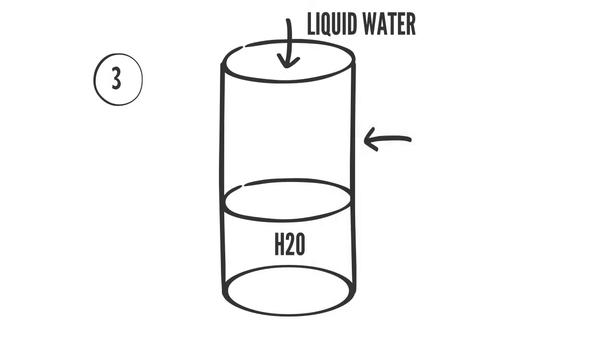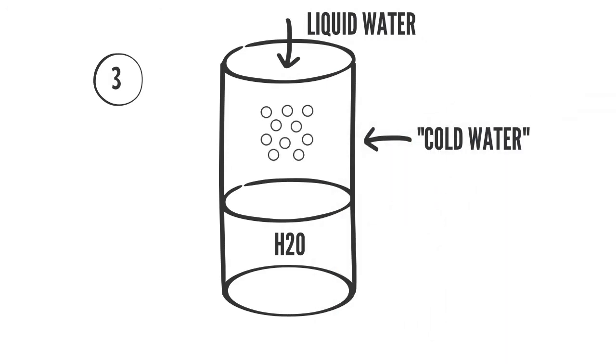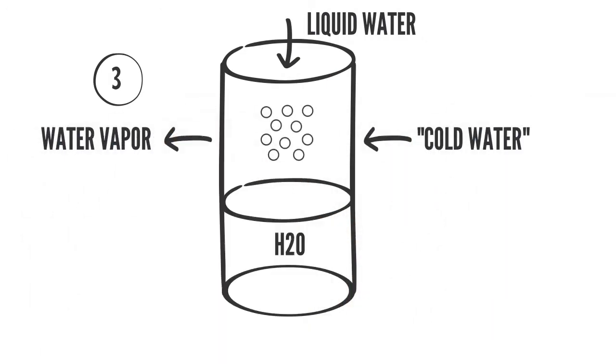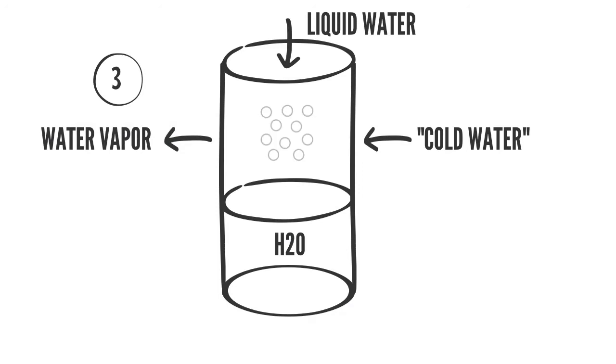The special ability of the lithium bromide to react with water also reduces the pressure in the third and fourth phases. The very low pressure in the third phase process chamber causes the condensed water from the second phase to evaporate after it has been heated by the ship's cold water circuit. It is in this process that the cooling itself is created and harnessed as a result of the phase transition from water to gaseous form.